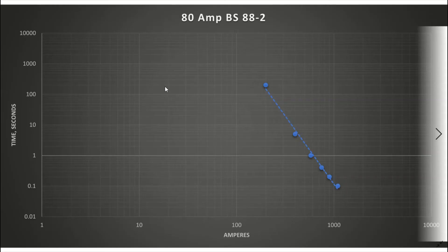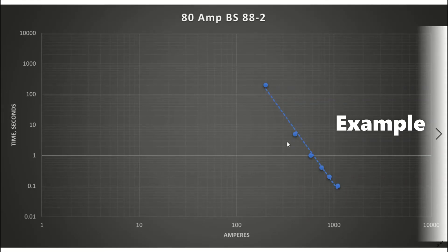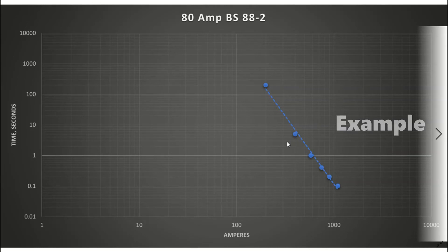On this next chart I have used the values for a BS88-2 fuse. So if we know the fault current we can plot the current on the chart, draw a line up to where it meets the curve and then across to find the time that it will take for the fault current to operate the protective device.